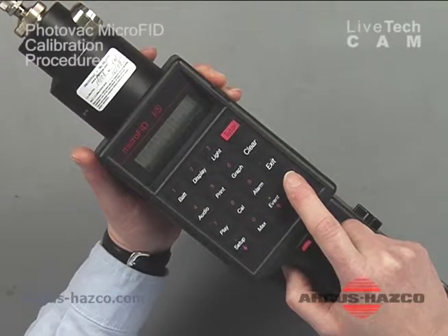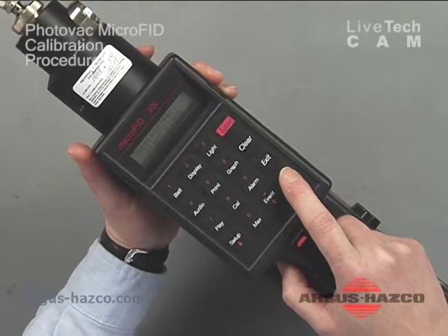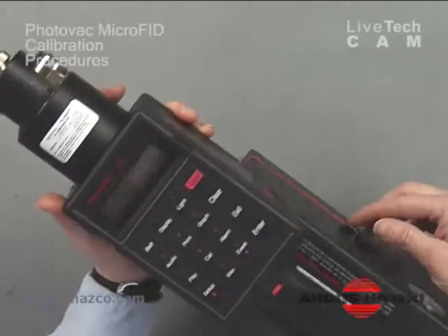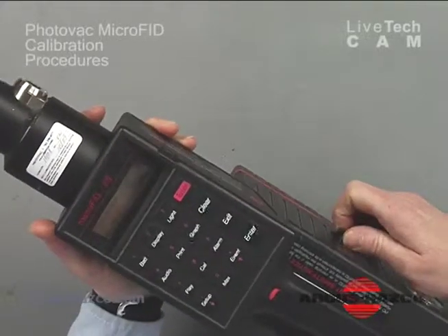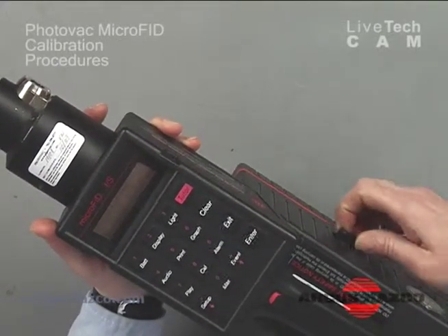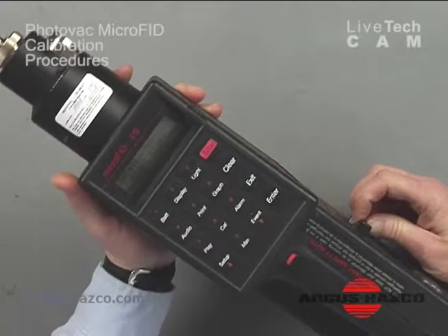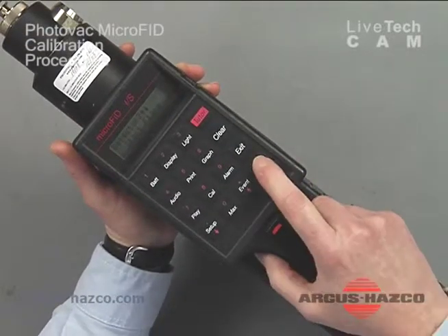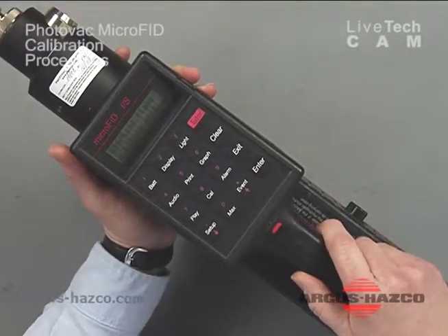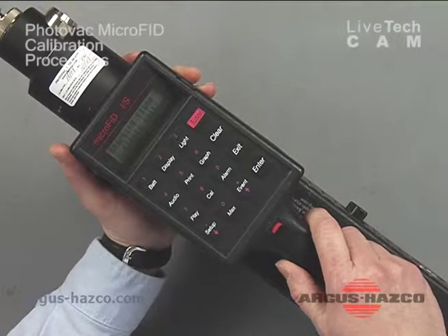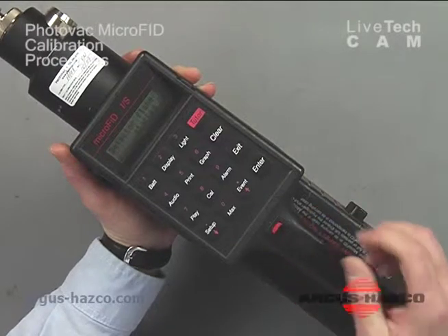Flame, start flame, and the first thing we do is turn on our hydrogen, and you just want to do maybe 2 turns of the knob. Once the hydrogen's on, you go ahead and press your enter key. You'll hear the pump start pumping, and the unit will say starting flame, please wait. And then the pump will stop, and then you'll hear a pop.